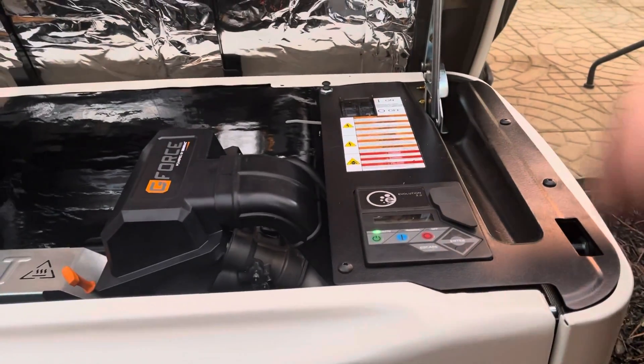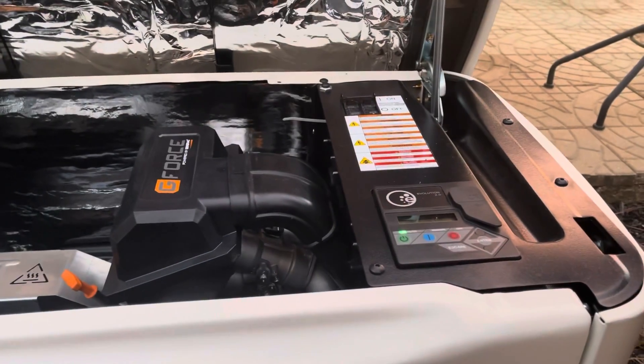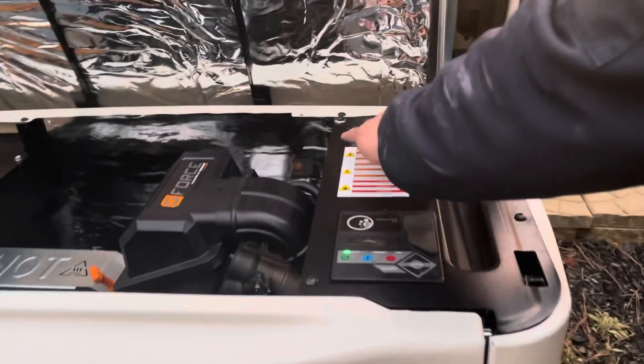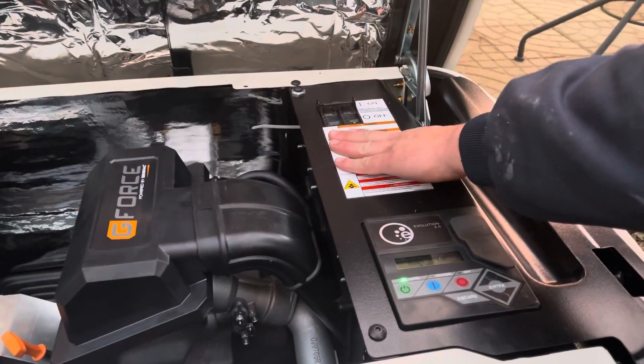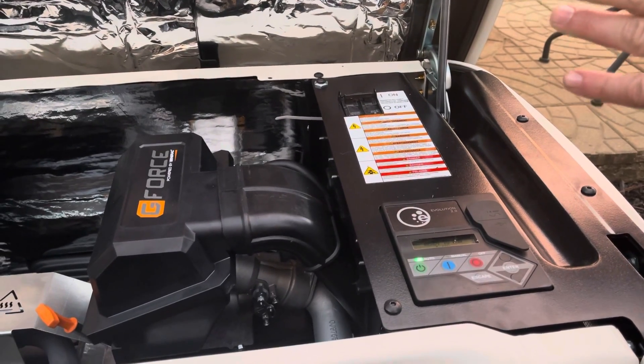Right now it's in auto. It works with that transfer switch — if it senses a power loss, that transfer switch tells this to turn on. This breaker stays in an on position. If it's in an off position and this generator's running, make sure it's not during your weekly cycle.